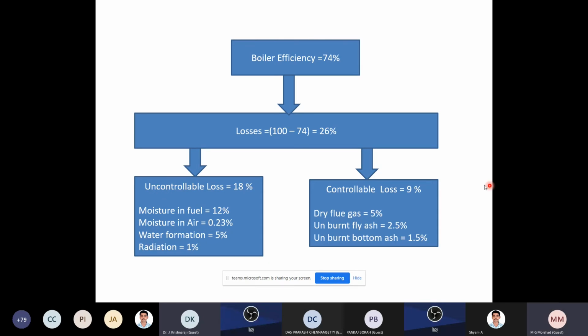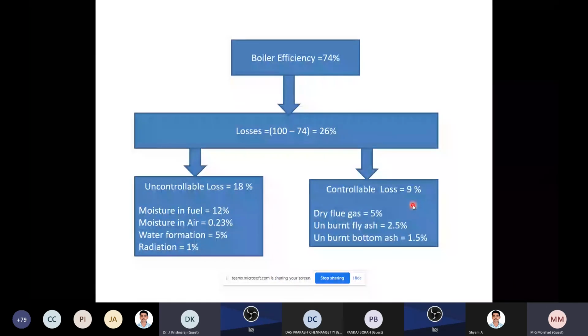And the controllable losses are only dry flue gas, unburned fly ash, and bottom ash. They are controllable because they depend on the excess air. If the excess air is more, the dry flue gas loss will be more. And if the excess air is less, unburned fly ash and unburned bottom ash will be higher, because the fuel will not be burned due to the lack of excess air. So if you have the right control over the excess air, this controllable loss can be reduced to some extent. But the other losses cannot be reduced. That's why there are two parts: one part is the controllable losses, the other is the non-controllable losses. Is it clear?